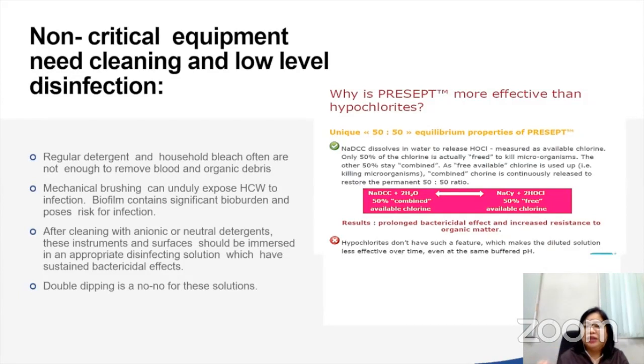So after cleaning, or what we call the babad, we have to soak. After soaking in anionic and neutral detergents, the instruments should be soaked in an appropriate disinfecting solution such as Precept. Precept is more effective than hypochlorites because it's sustained release. 50% stays initially as free available chlorine, but the other 50% combined will become available later on as it stays soaked. So there's a prolonged bactericidal and virucidal effect, and therefore better infection control because you make sure that the virus is killed.